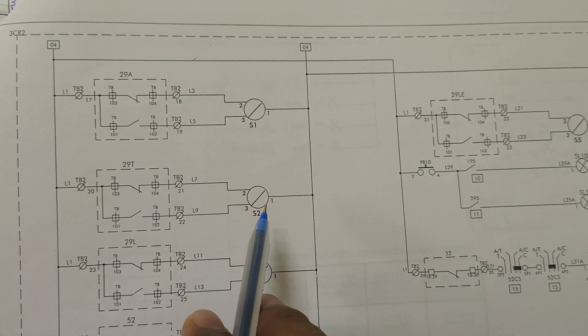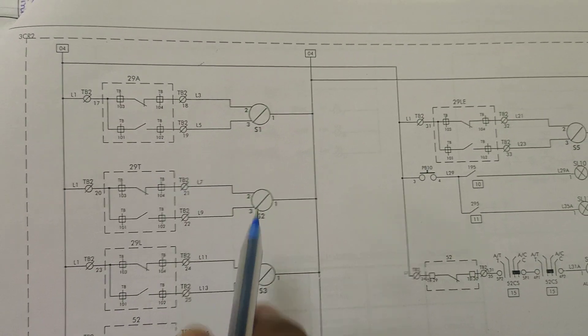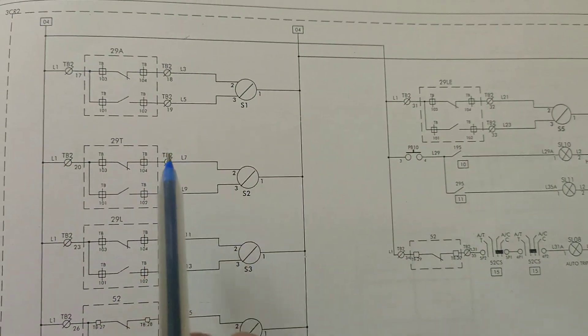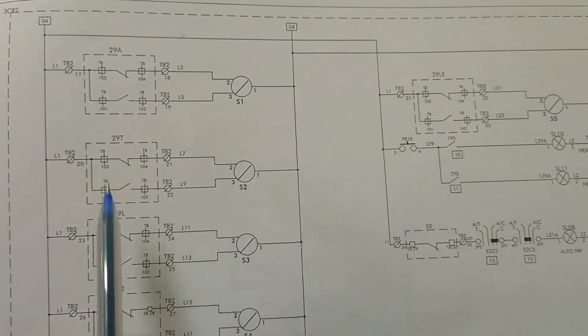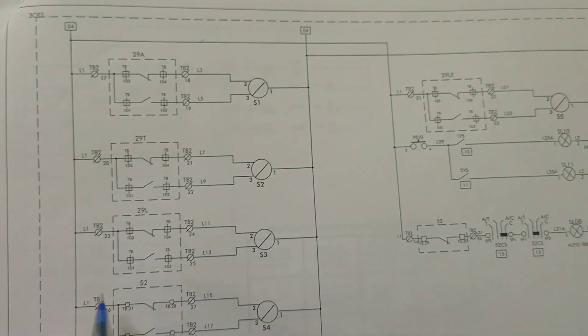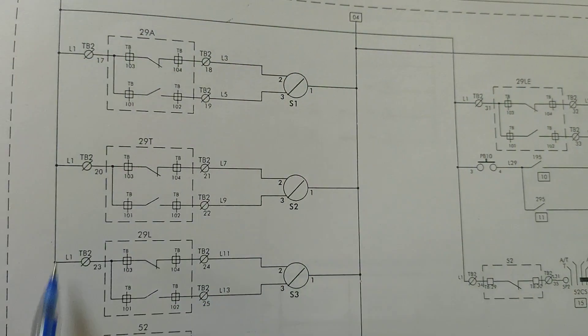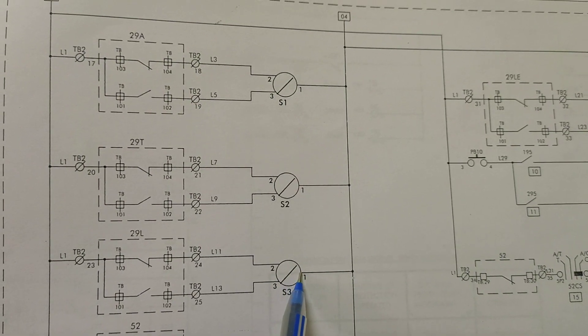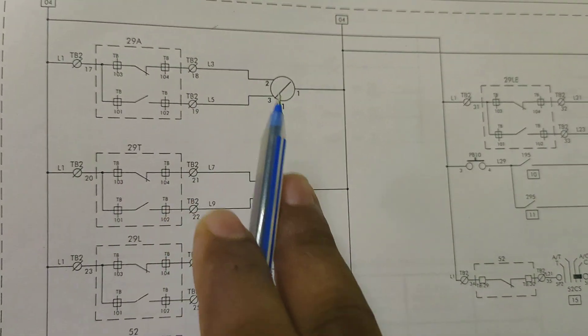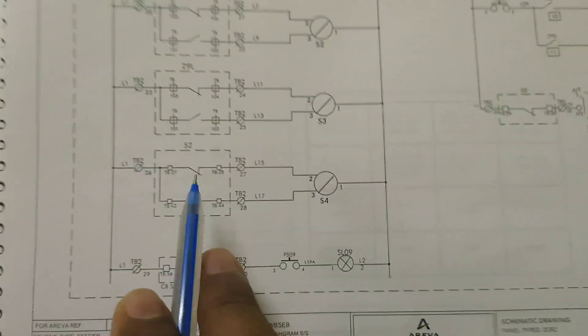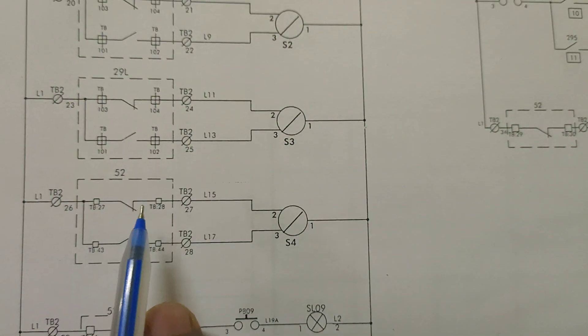After utilization or proper completion of the job, if we want to open the transfer bus side isolator, this contact will be NO and this contact will be NC, and it will go to the OFF position. From the control panel we can observe that the line side isolator has been opened successfully. This is 29L — the line side isolator — with the same function. L1 is the positive side and L2 is the negative side.